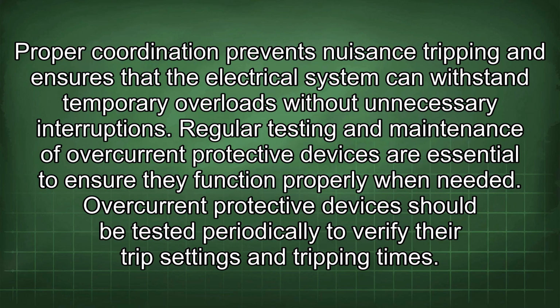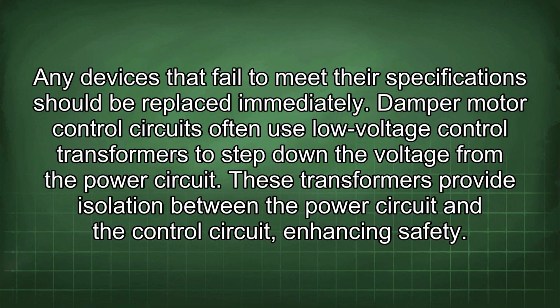Regular testing and maintenance of overcurrent protective devices are essential to ensure they function properly when needed. Overcurrent protective devices should be tested periodically to verify their trip settings and tripping times. Any devices that fail to meet their specification should be replaced immediately.